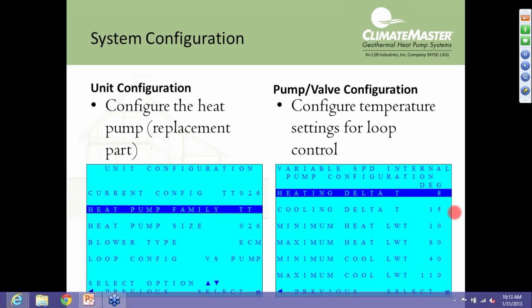All right, unit configuration. Under unit configuration, this is where you configure it for the heat pump family, whether it's a TE, TZ, TES, and so forth, and then the heat pump size. And again, I want to emphasize this is already done for you at the factory, so you should not have to go in and change it unless you're changing a control board or you're following up on a service call that somebody else was out on and maybe made a change here that they shouldn't have.